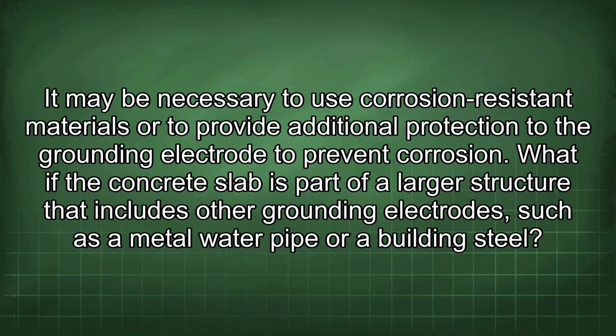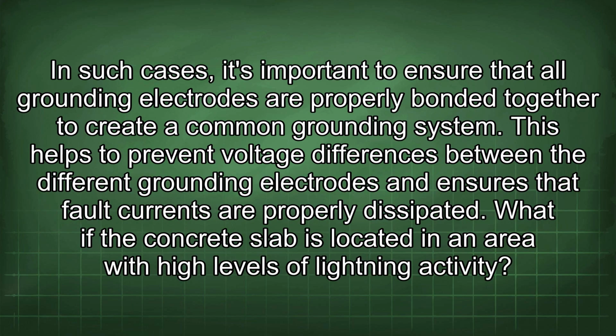What if the concrete slab is part of a larger structure that includes other grounding electrodes, such as a metal water pipe or a building steel? In such cases, it's important to ensure that all grounding electrodes are properly bonded together to create a common grounding system. This helps to prevent voltage differences between the different grounding electrodes and ensures that fault currents are properly dissipated.